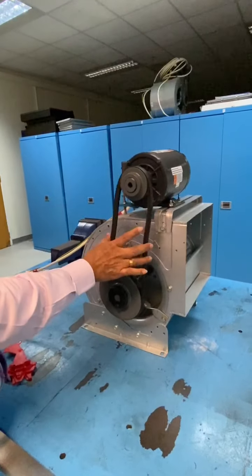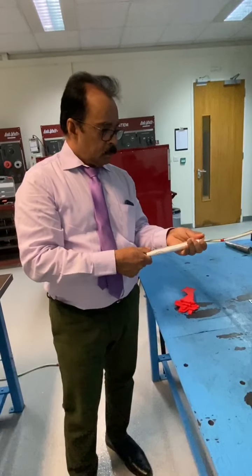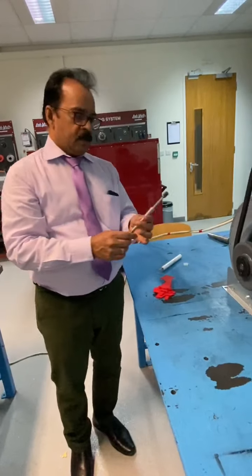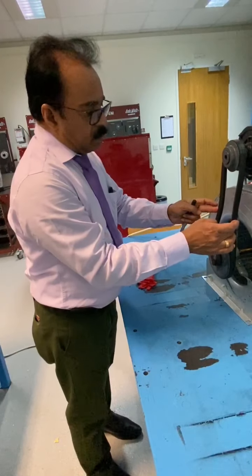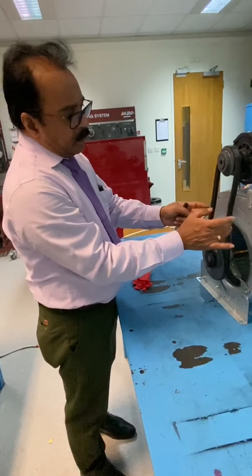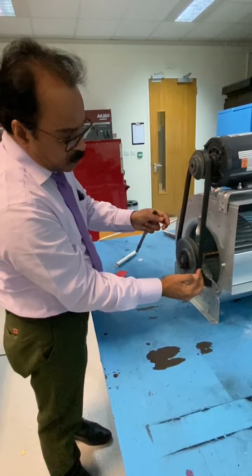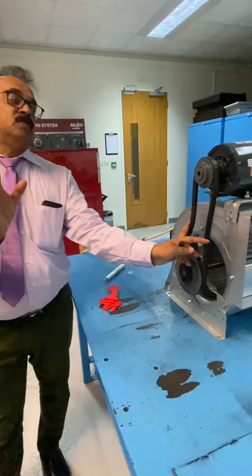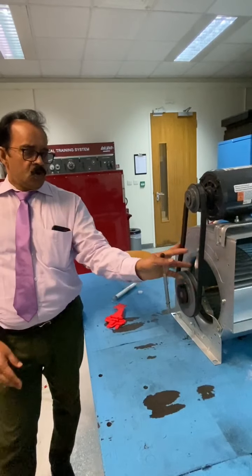And also how you test the tension, there is a tensioning device. This is the tensioning device, belt tensioner. So here we can press like this, and then the deflection here, by getting a steel rule here, first put it there, and then tension. Then this gap between these two is according to the specification. If the gap is too big, it means the tension is not correct. So you can check from here.